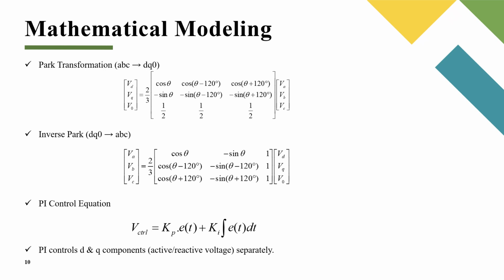Mathematical modeling. This slide shows the key mathematical tools used in DVR control. Park transformation converts three-phase ABC voltages into DQ0 components, simplifying control by aligning the signals with a rotating reference frame. The inverse Park transformation converts DQ0 signals back to the ABC form for inverter switching. The PI control equation adjusts the system response based on the error signal, balancing a proportional and an integral term to ensure both stability and fast correction. The D-axis typically controls active power, while the Q-axis handles the reactive power.